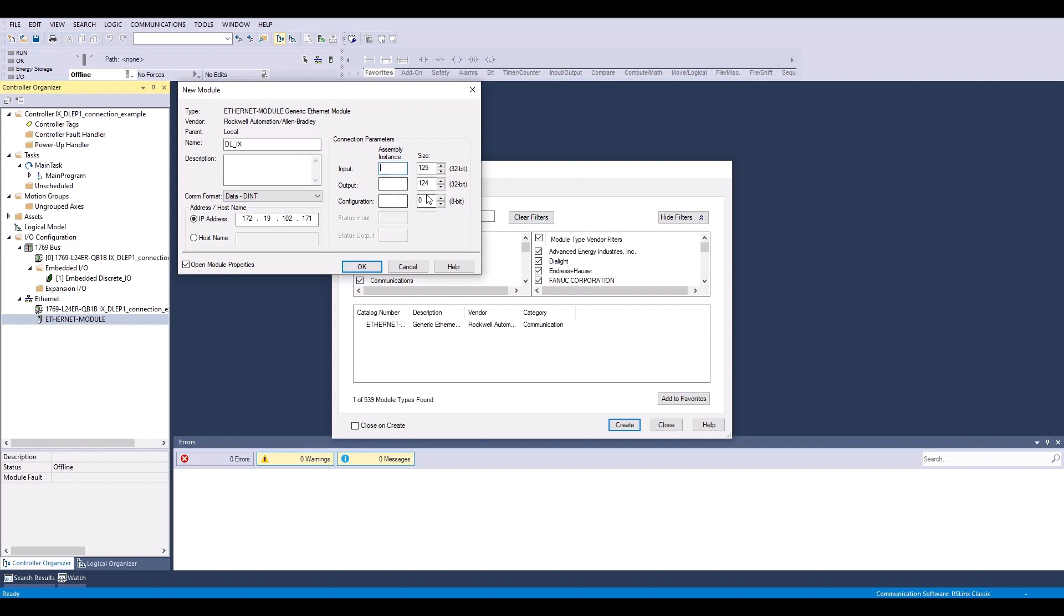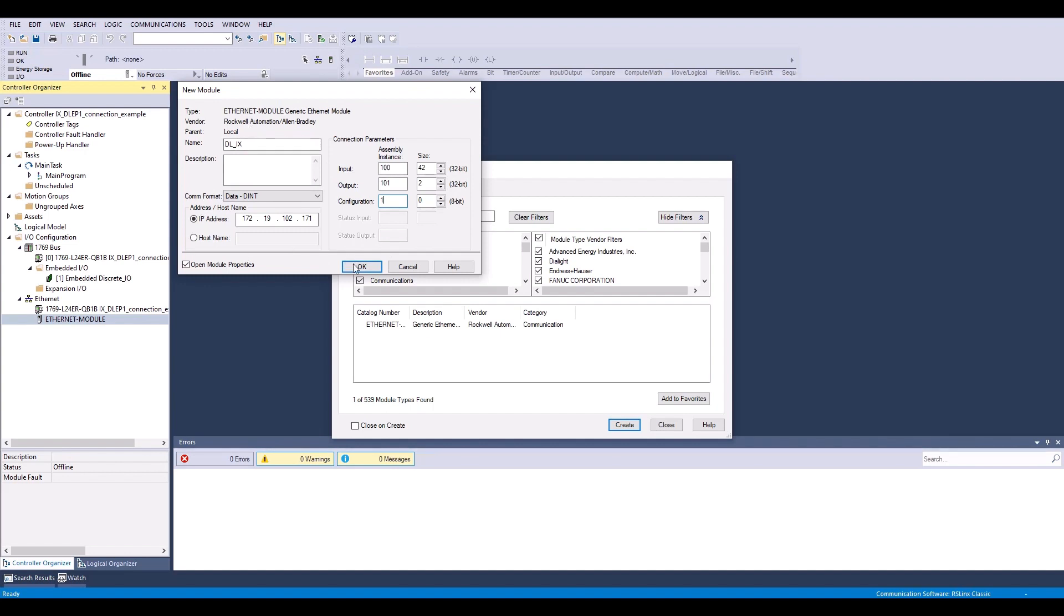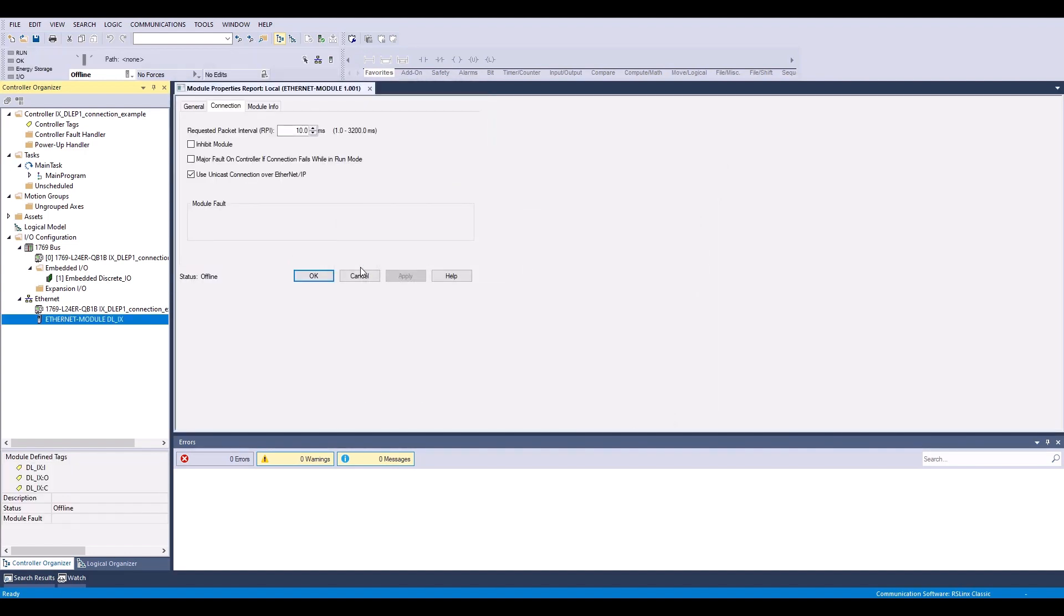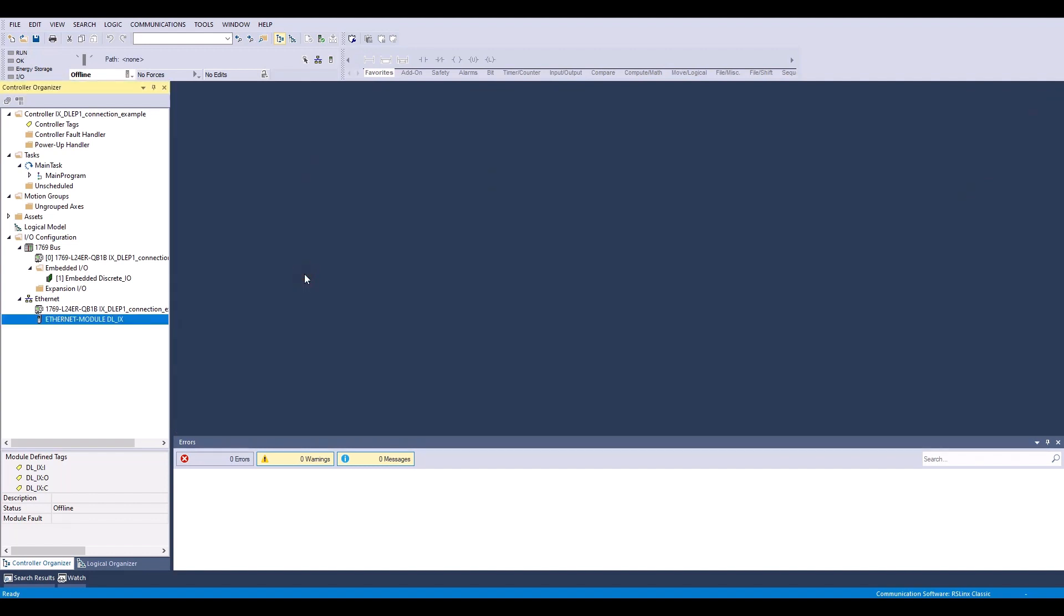Next, I need to adjust my input assembly instance and size. So this is 100 with a size of 42. My output assembly instance is 101 with a size of 2. And my configuration is 1 with a size of 0. So now that my generic Ethernet module properties are set, I'm going to hit OK. And hit OK again. And now you can see I have my module over here.